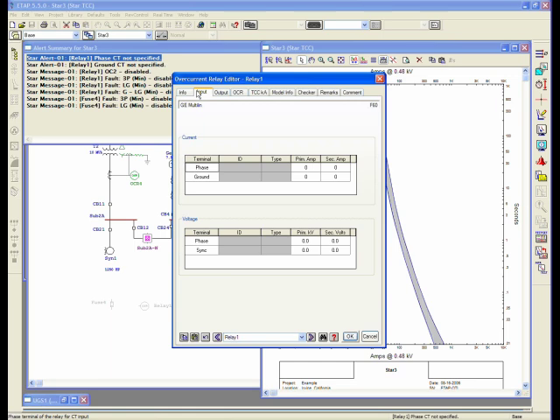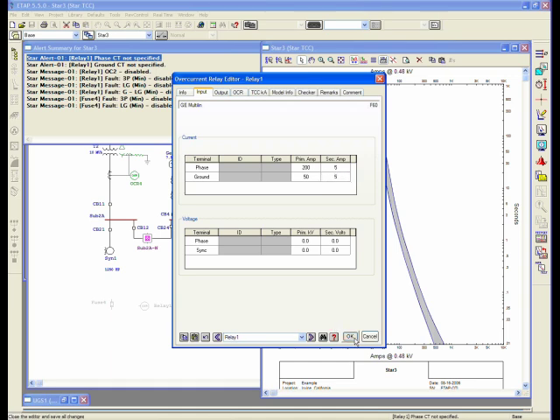We can add directly the CT information to the relay editor as shown here. I can click in here and type in 200 to 5 for my phase. And if I want to use my ground also, I can do the same, and let's say I select 50 to 5. And once I do this, the relay curve will show up.